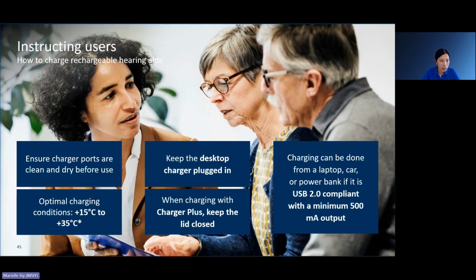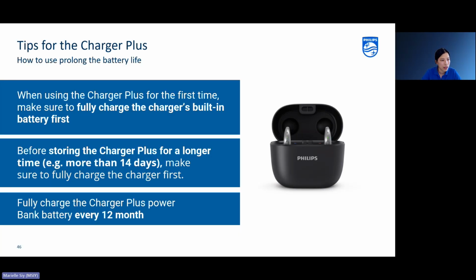And of course, I mentioned all of these before. The Charger Plus is a bit trickier because you have to do things like make sure the lid is closed, make sure it's inside the acceptable temperature limits, and so forth. And when you're using the Charger Plus for the first time, make sure to fully charge it to 100%. Before storing the Charger Plus for more than 2 weeks, make sure again to charge it to 100%, and to charge it at least once every year, assuming that it's at 100%. These are things which will make sure that the battery health of the power bank remains good.